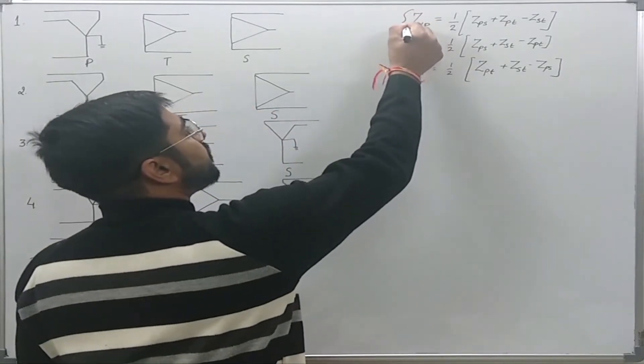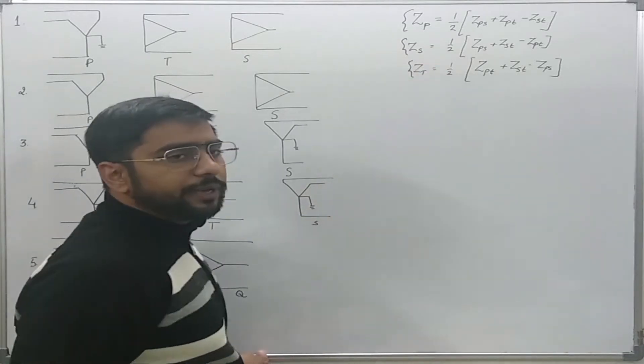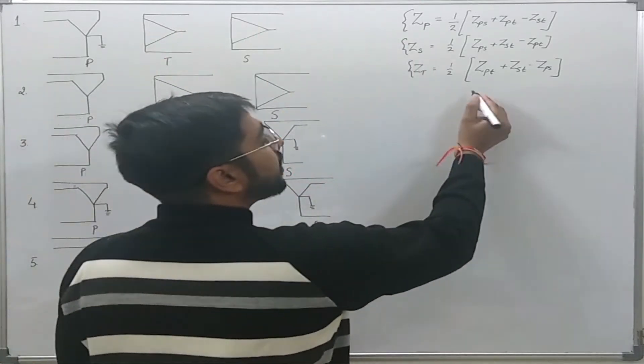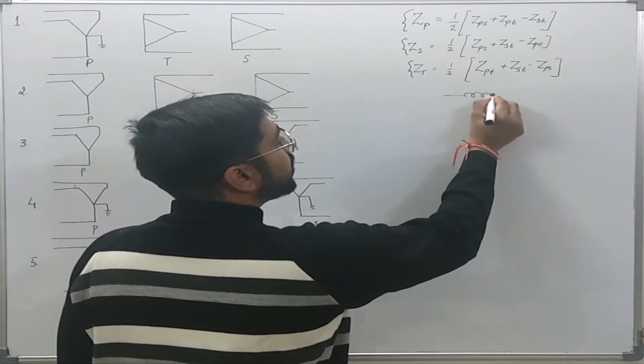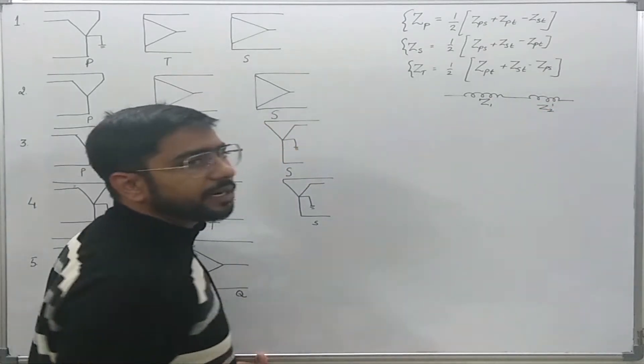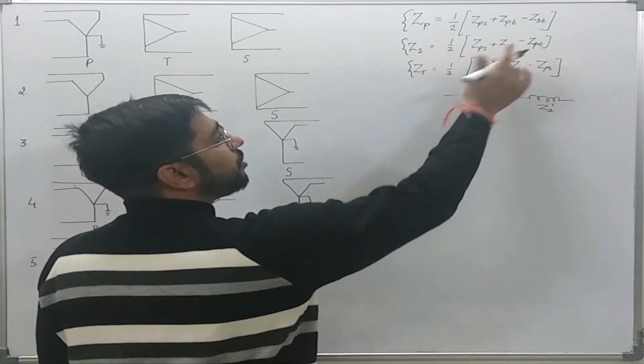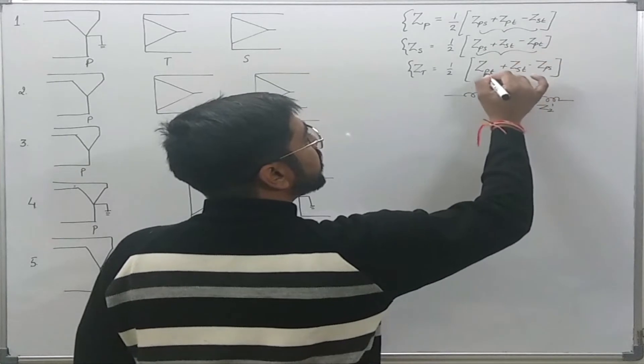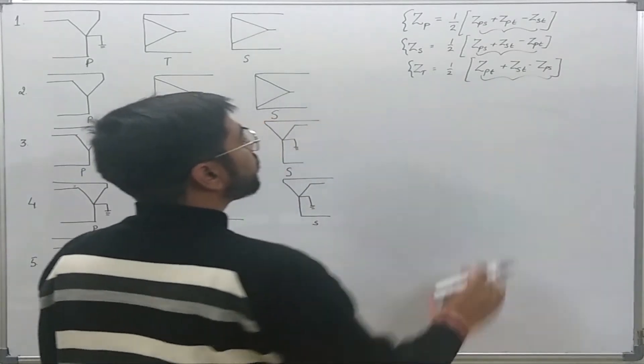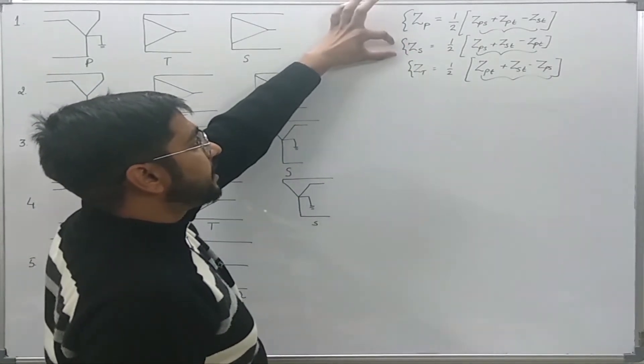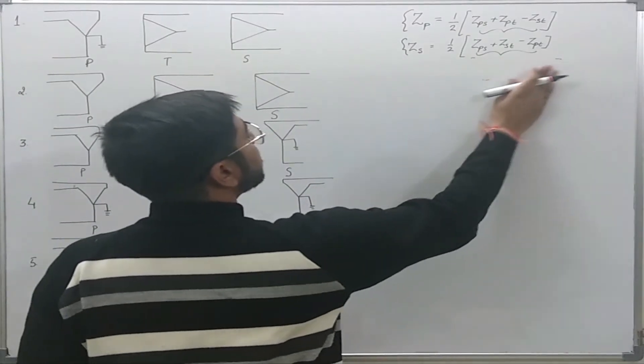If we use a proper voltage and VA base, then all impedances Zp, Zs, and Zt will be referred to one of the windings — just as in a two-winding transformer we take Z1 and Z2-dash, where Z2-dash is the secondary impedance referred to the primary. Using proper bases, all values are on one side of the transformer. I will use these Zp, Zs, and Zt in the equivalent zero sequence network for these connections.